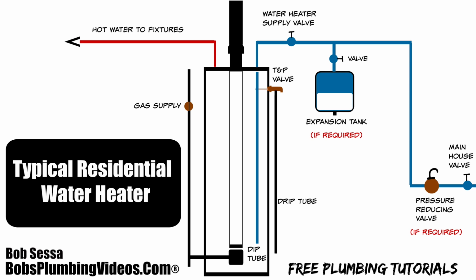Now, we have incoming water pressures here of anywhere in the low 40s to, I've seen them as high as 80, which are deemed pretty safe water pressures. So there's no need for us to have pressure reducing valves. But to our California friends, I know in California that they have very high incoming water pressures, and they are required to have pressure reducing valves. And simply what a pressure reducing valve does is reduce the pressure on the outlet side to a safe pressure. I don't know what that pressure is in California. So let's just say they set it anywhere between 40 and 80 as an example. I don't know for sure.